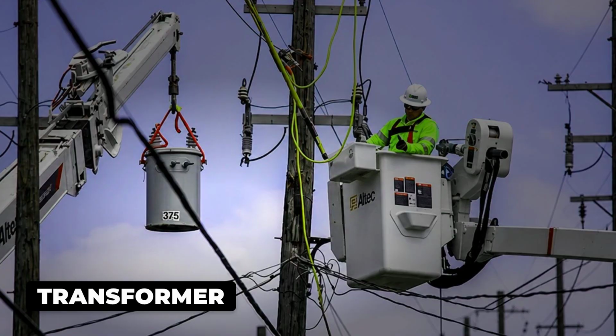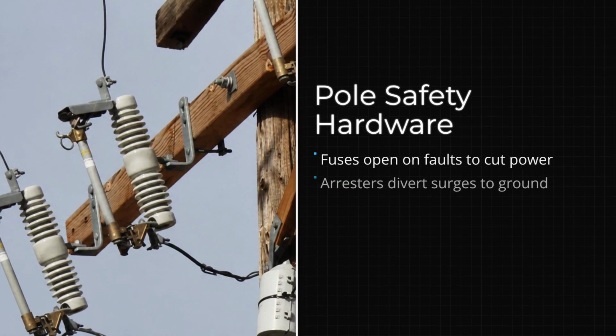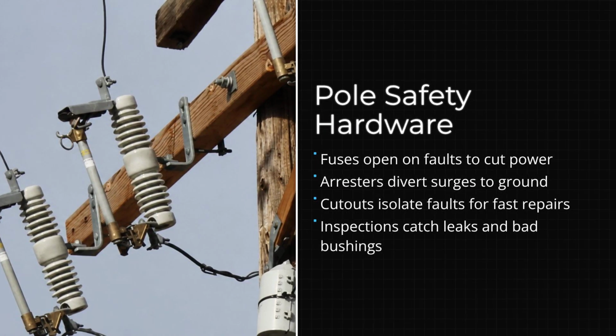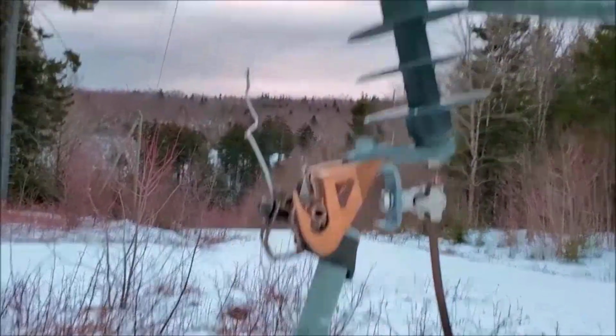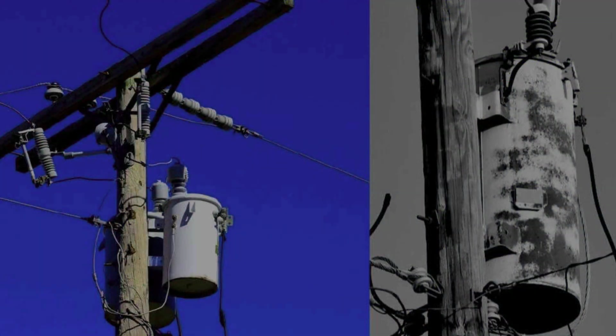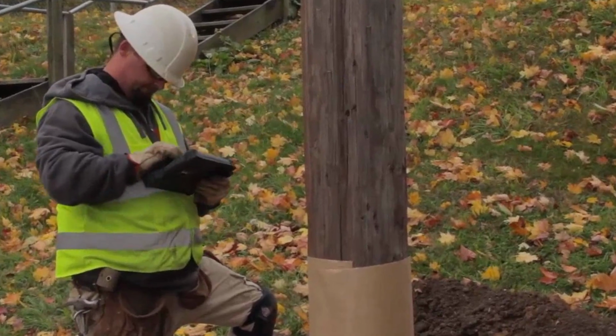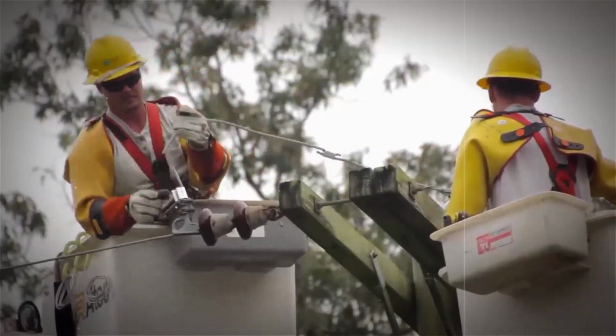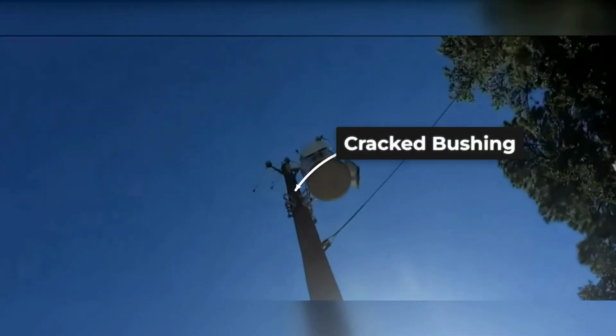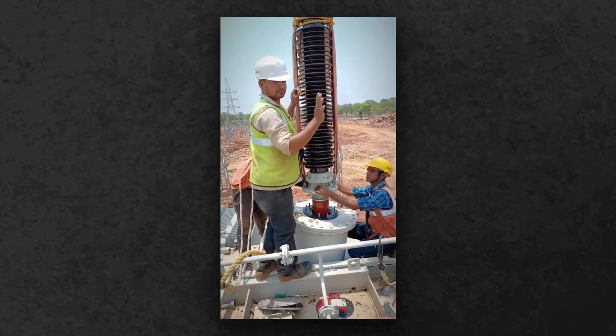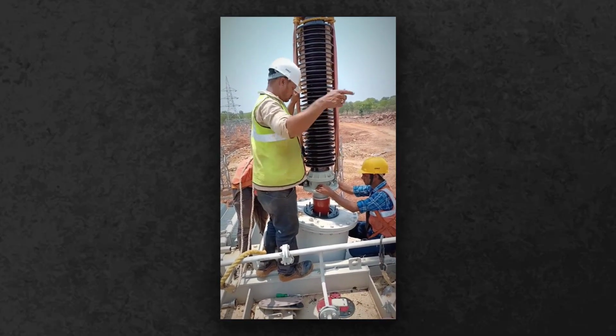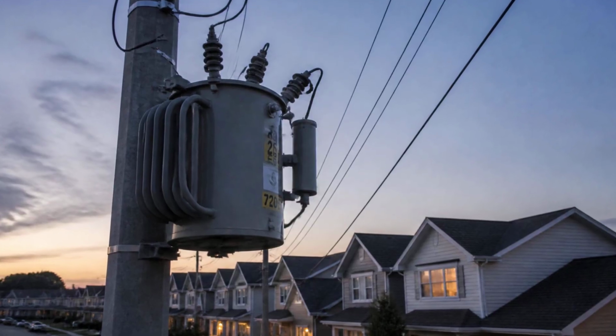But even with this self-cooling design, pole transformers cannot operate completely unprotected. Utilities buffer these devices from grid instability using external safety hardware, including fuses, lightning arresters, and cutout switches designed to isolate electrical faults instantly. While built for a service life that often spans 30 to 40 years, these machines require structured monitoring. Linemen conduct regular visual patrols, scanning for oil leaks, cracked porcelain bushings, and physical wear.